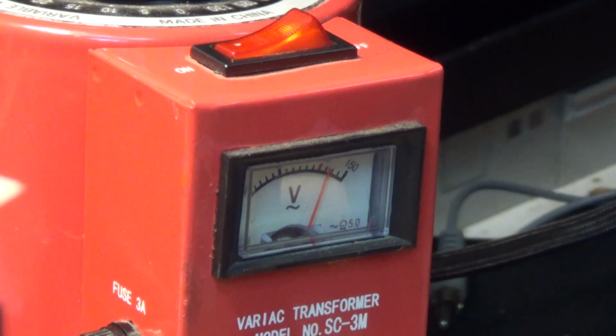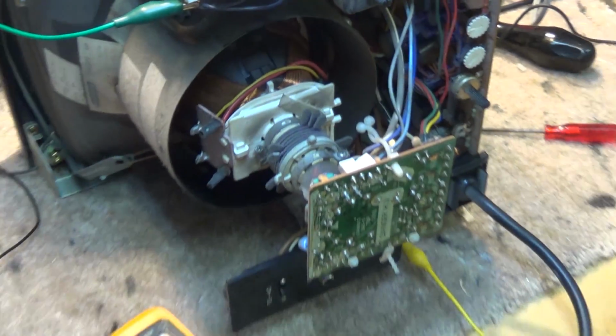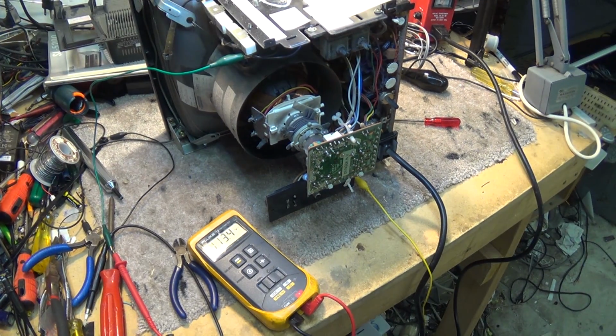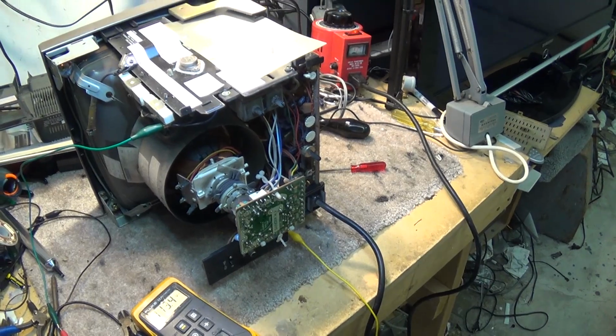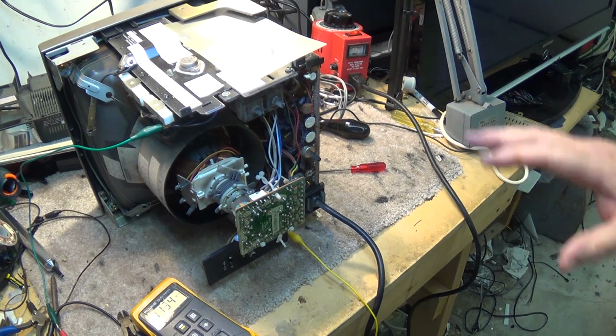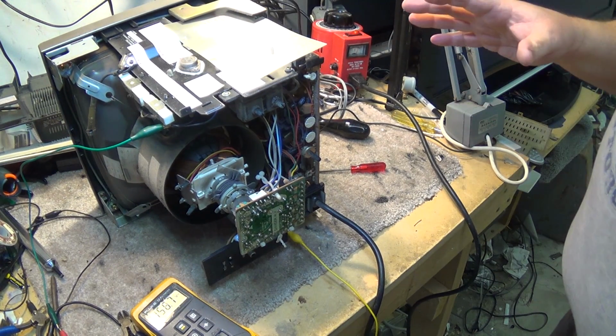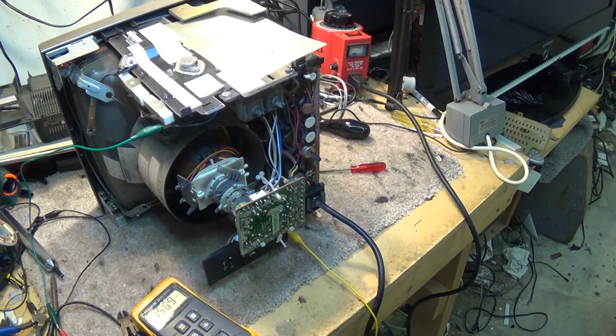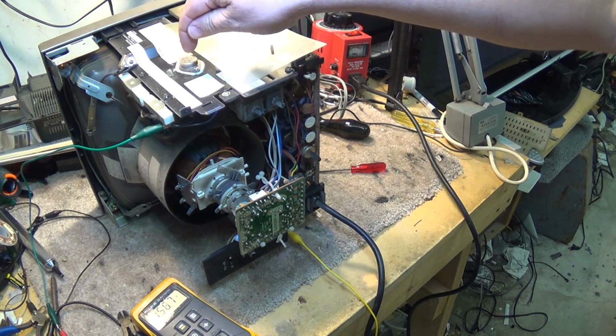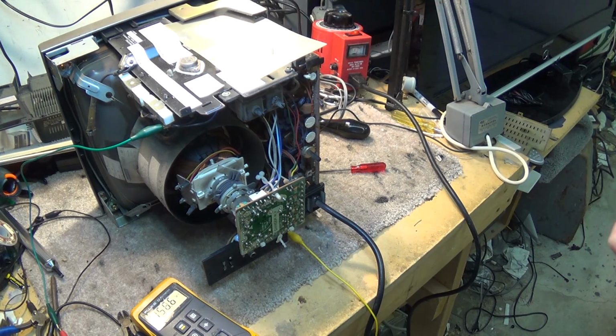Okay, 125 volts going in. I've got 113 volts. My regulation is working now, right? Our normal voltage here is 120. So let's see how high I can go on this thing before it actually shuts down. The regulator will only work to a certain degree because it is a shunt regulator. So if I get beyond the control ability of the transistor here, the voltage is going to go too high and it is going to shut down.